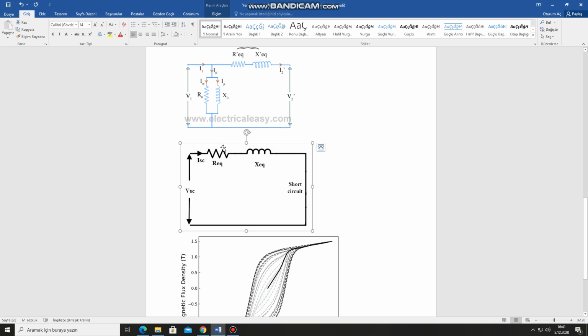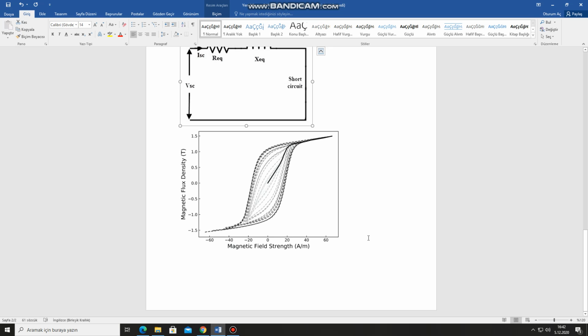It's valid for any applied voltage, but in this case our frequency is constant. Please keep that in mind. And especially this one refers to the leakage inductance. This is also independent from the applied voltage in our case, so taking one measurement for the short circuit model is enough to characterize the copper losses and leakage fluxes. So this was the last question.